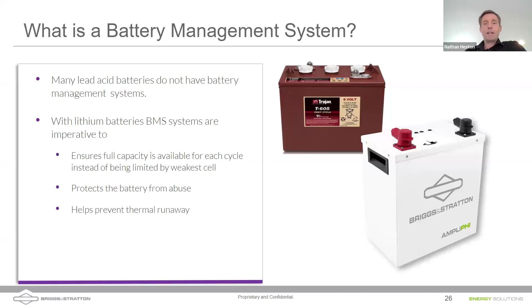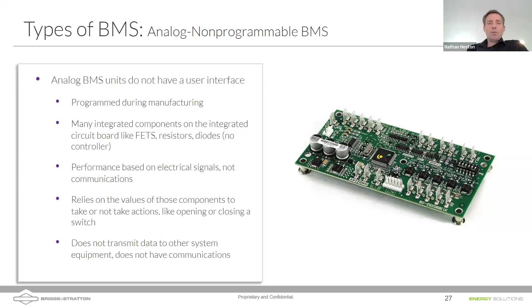There are different types of battery management systems. An analog BMS does not normally have a user interface, so the factory presets the equipment. Yes, you have integrated things like FETs to turn on and off current in the event of protection events, but for the most part you don't have programmability beyond what the factory sets in the beginning. They also don't really have the ability to transmit data to other system equipment like the inverter.